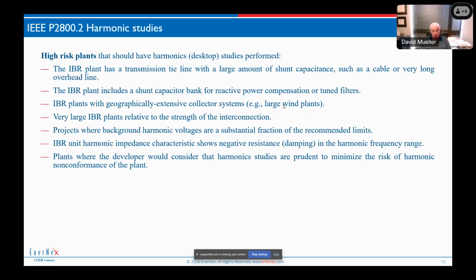If a project has a high background voltage harmonic, if we're already over the IEEE 519 voltage limits, it might be nice to have a pre-installation harmonic survey that shows us what we get before we even go there. That might tell us that this isn't an area where models are going to help us understand the impact of the plant on the grid. And if we have an IBR unit that has negative damping in some harmonic frequency range, then we want to make sure we don't have that resonance condition, because we don't want to have that problem. I'll show an example of that in a moment.